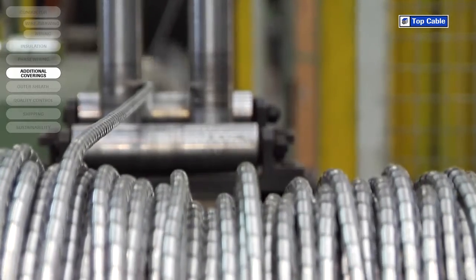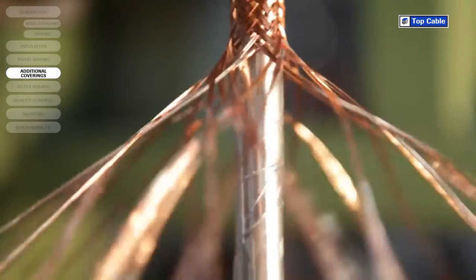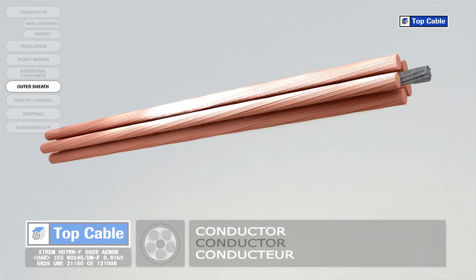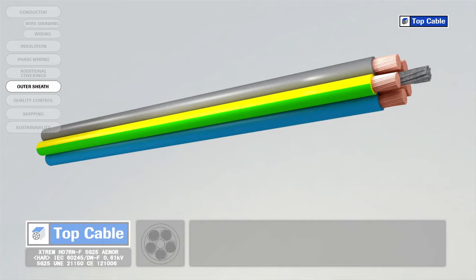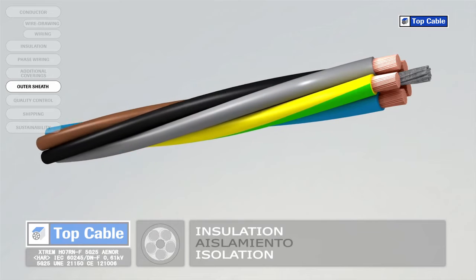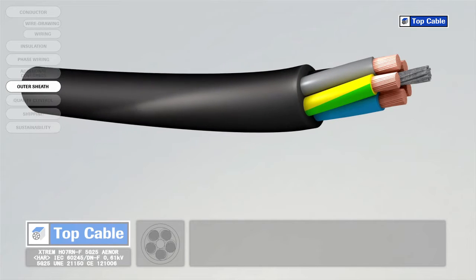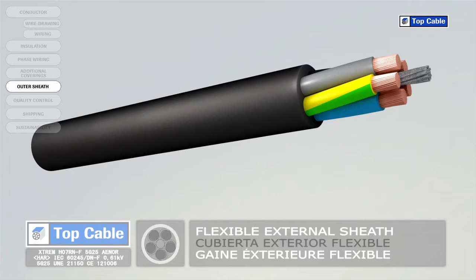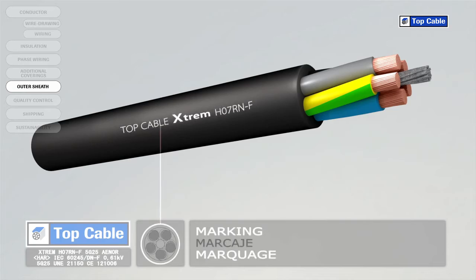The armor is made from steel or aluminum and can come in the form of metal strips, wires, or braids. Cables usually have an outer polymer covering for protection. This is called the outer sheath. The sheath protects the conductors and their insulation from external elements which may change their electrical properties, such as moisture.